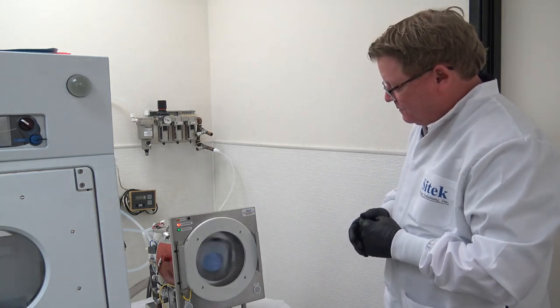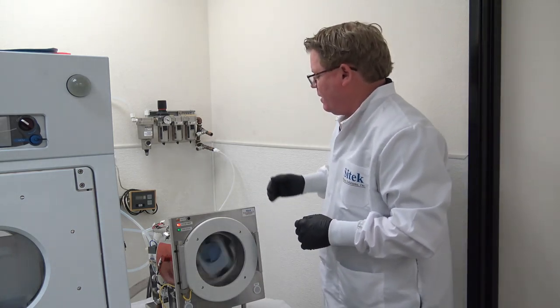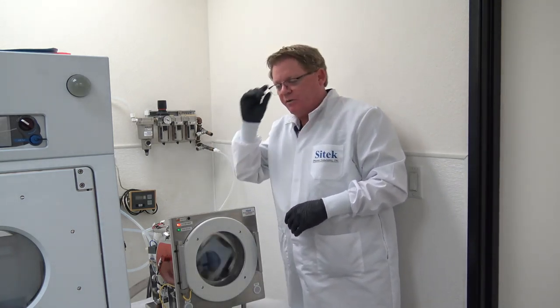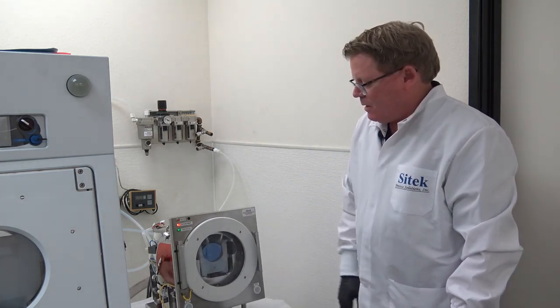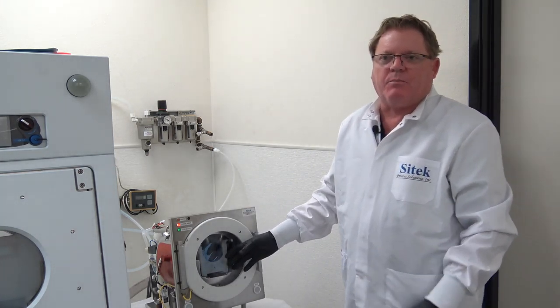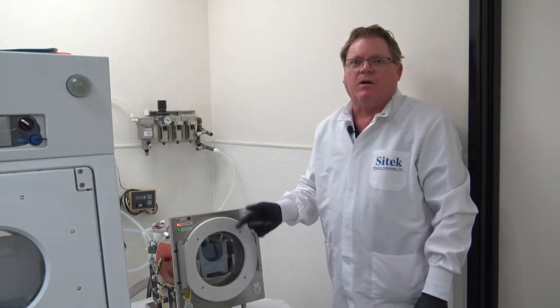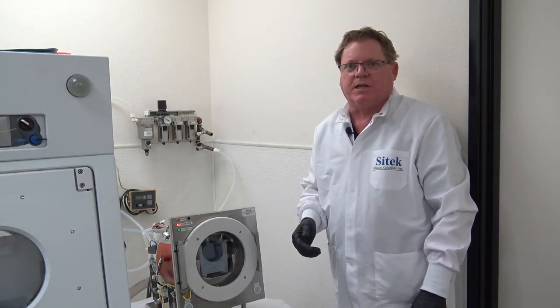Okay, we'll be ending pretty soon. At the end of the process, there's something back here called the Rotor Stop Positioner. It has a cam assembly. It'll shoot out and roll against the cam, find the flat and upright to what we call home position, and the door will release. The ST has a built-in timer before it releases. The S and F model will release once the RPM goes down to zero.